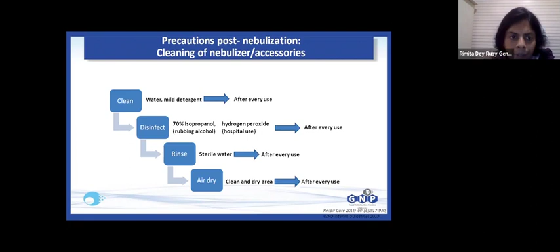So clean with water and mild detergent after every use. You disinfect with 70% isopropyl alcohol or hydrogen peroxide after every use. Your institution should have a good cleaning protocol for nebulizers as well. You have to rinse with sterile water, and you have to clean and dry the area after every use. So hospital grade cleaning and disinfecting agents are recommended for all horizontal and frequently touched surfaces.